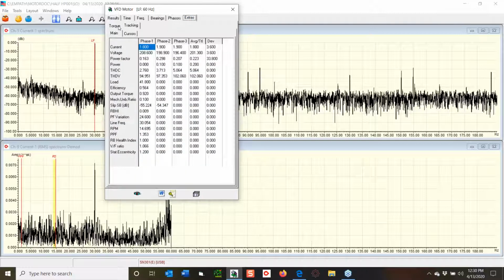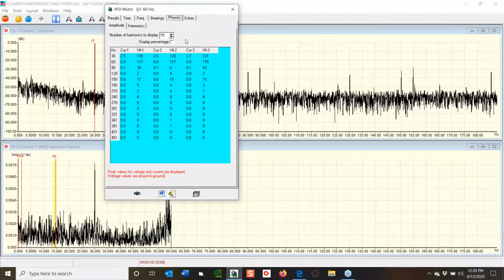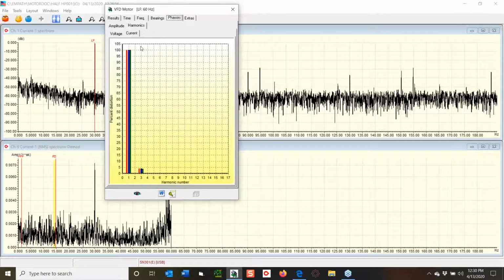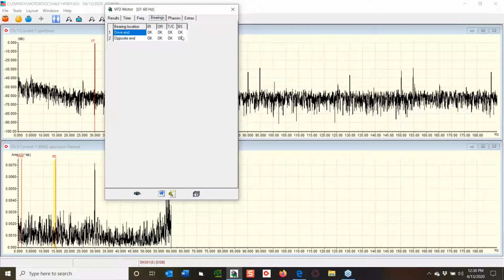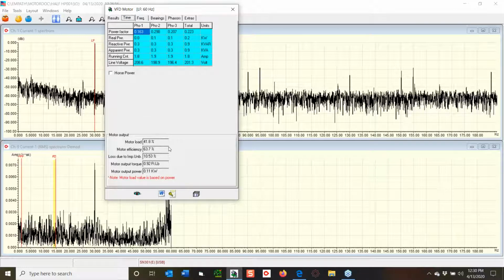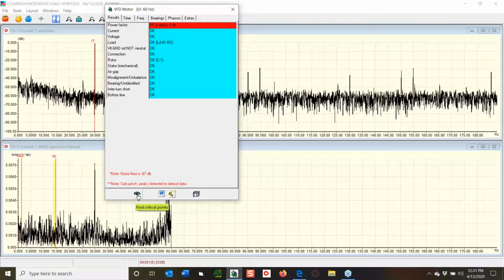Okay, and I can go in and take a look at all my different stuff. So like this here, tracking, this is what I trend with. Phasors, this is my harmonics, so there's my voltage harmonics, my current harmonics. This is what my bearings look like. This is what it all calculated as far as my line current, running speeds, and so on. This gives me what it thinks the efficiency is and the load. I can switch everything over to horsepower if I want. And then my results, from here I've got the ability to rescan everything.